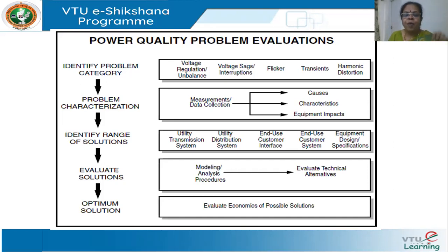And they have some observations. What are the observations like? Some relays are tripping. Suddenly some relays trip. So the first thing is the operator will try to see locally what is the analysis. Then the operator finds that he can't find the problem. Everything seems to be correct. So the operator is not able to identify the reason for this unnecessary or uncalled for relay tripping. Or it could be that suddenly the motor starts stalling. The speed reduces and then picks back and comes back to normalcy. Or they observe excessive vibrations at certain times during the day.